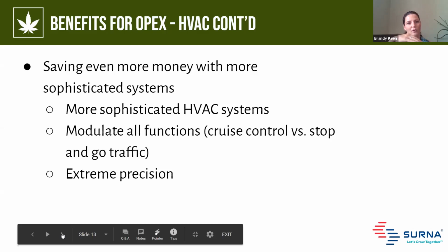When you're just turning things on and off, your controls trend line, or the performance in the room, looks like up, down, up, down, up, down. What happens is the set point's at 76 degrees Fahrenheit, or humidity set for 55, so it doesn't come on until that's out of whack, and doesn't turn off until you bring it back down. So it drifts out, comes back, drifts out, comes back.